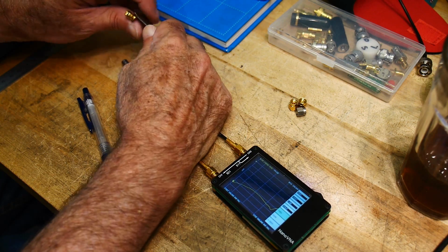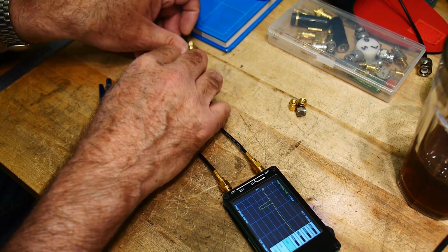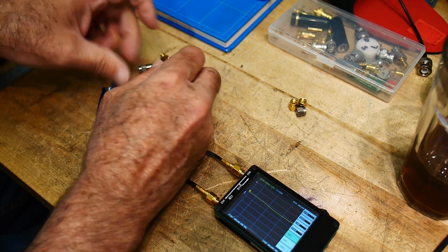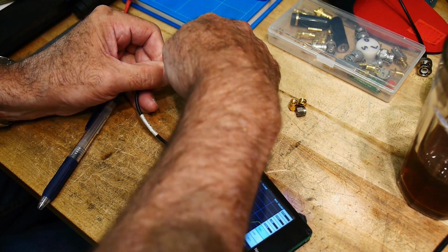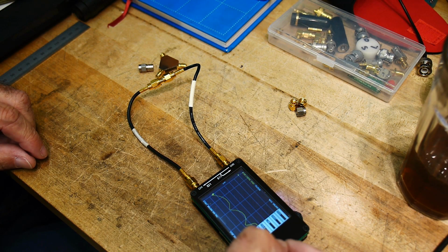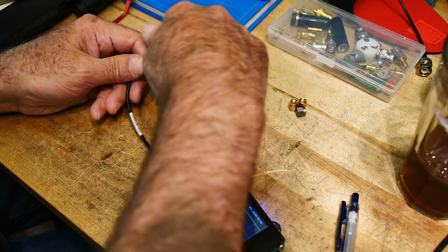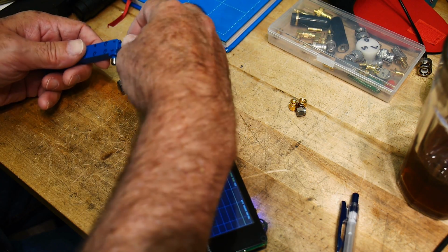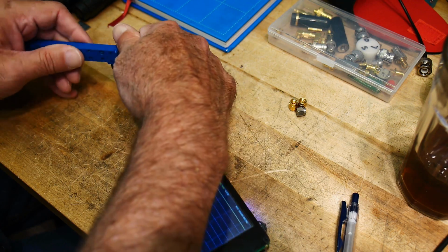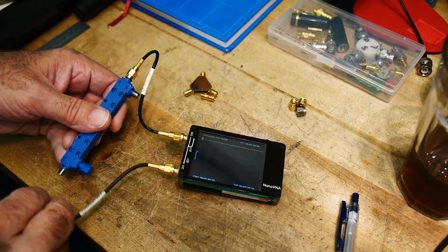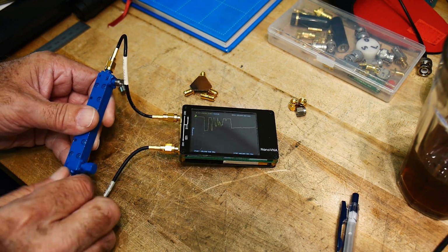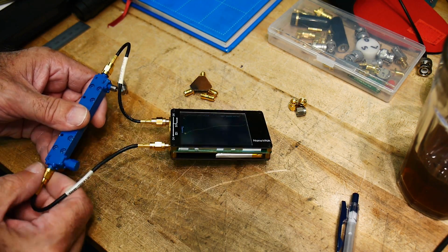Isolation. And then we're going to do a through measurement, which is the S21 measurement. And I have a short coupler. All right, and we'll do the through measurement. Done. Save zero. Okay. So the first thing that we want to do is take the channel zero port, put that on the in, and the channel one port, put that on the out, and we will put a load on the coupling port.